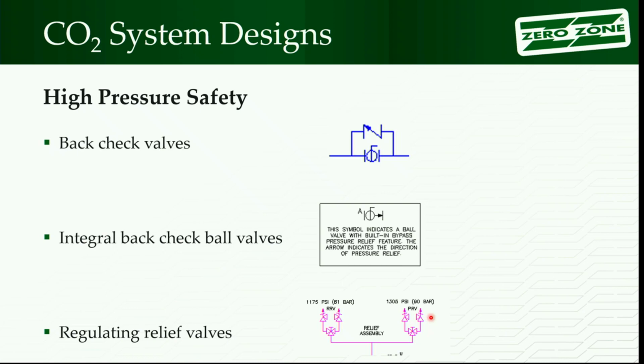CO2 is not the only one. If you have a fire, tanks explode, people die. So everybody knows to put on relief valves. Those are all sized for fire, so they'll let a lot of gas out when they open. That's what they're designed to do. They're designed to drop that pressure down in the event of a fire. Well, if your pressure's going up because you lost power, it's not a fire, it's kind of creeping up a little bit at a time.